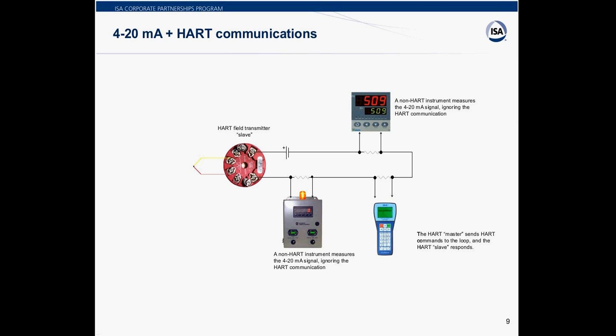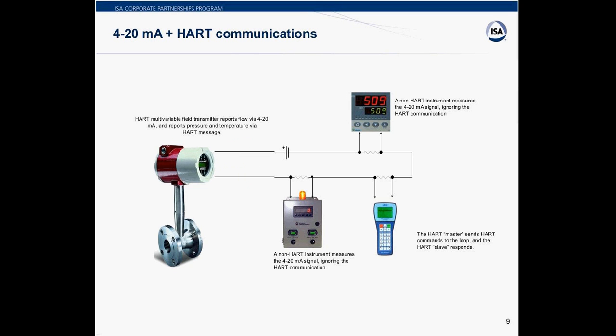Some HART transmitters can measure more than one sensor at a time — these are called HART multivariable transmitters. This is a picture of a gas flow transmitter that also measures the pressure and temperature of the gas flowing through it. The flow measurement is called the primary variable, and it controls the 4 to 20 milliamp loop current. The pressure and temperature measurements are the second and third variables, and these measurements are transmitted digitally in the HART message. A HART master flow computer could be used on this loop to measure all three variables and compensate the flow measurement as gas pressure and temperature change, resulting in accurate flow measurement under a wide range of conditions.